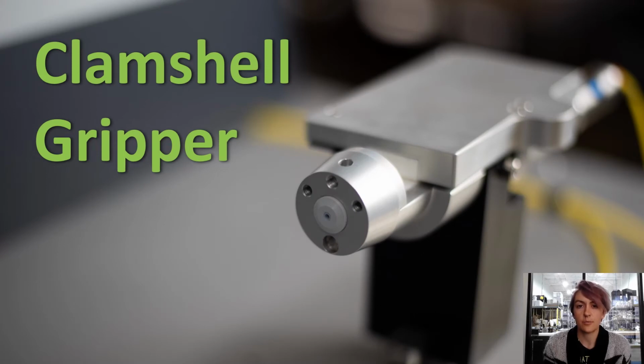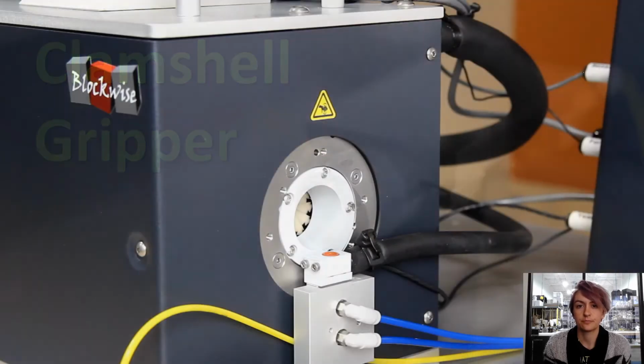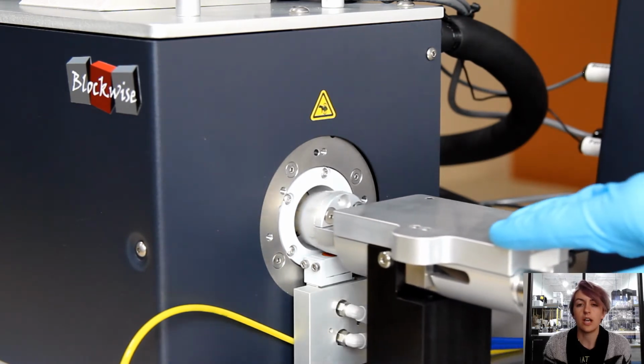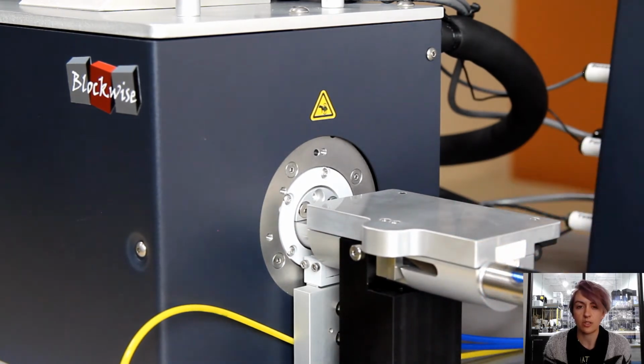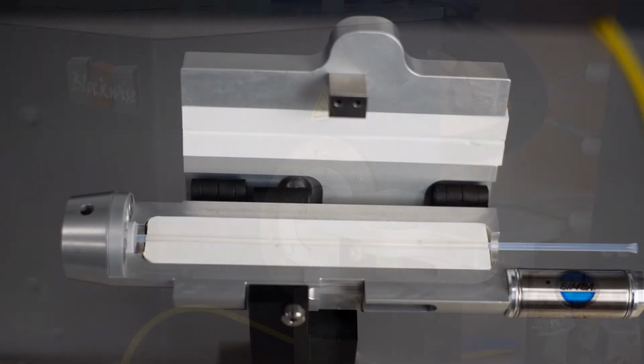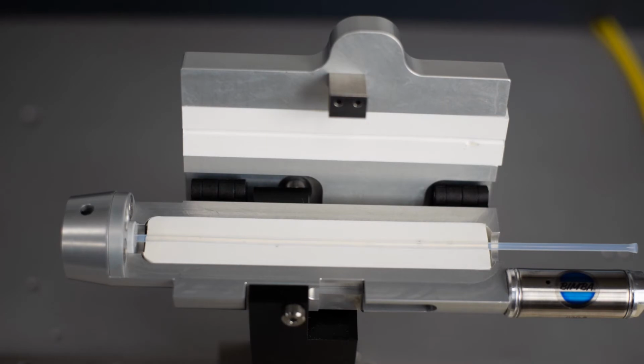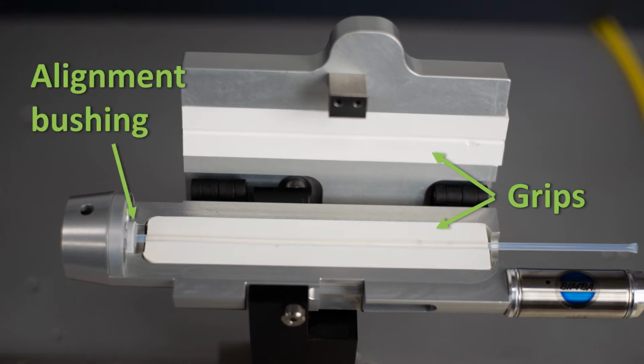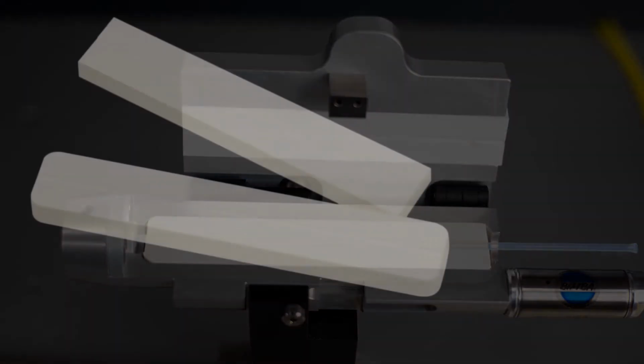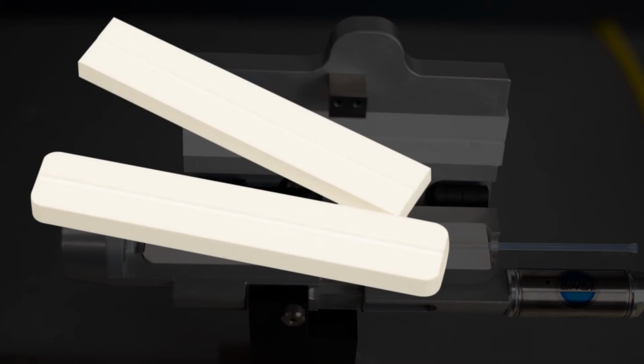First, we should discuss the clamshell gripper. The clamshell gripper aligns the catheter with the crimped stent inside of the compression station. It firmly holds the catheter during the loading process. The carrier will need to have custom tooling made to hold your specific product. So this includes the grips, which hold the catheter and prevent it from slipping during loading, as well as the bushing that aligns the catheter with the opening of the station. The grippers are custom molded pieces of silicone that fit inside the carrier and are sized a little below the outer diameter of your catheter.